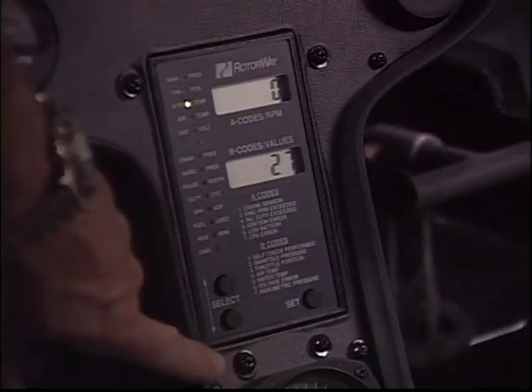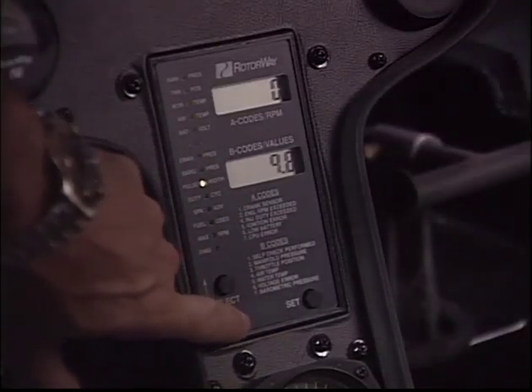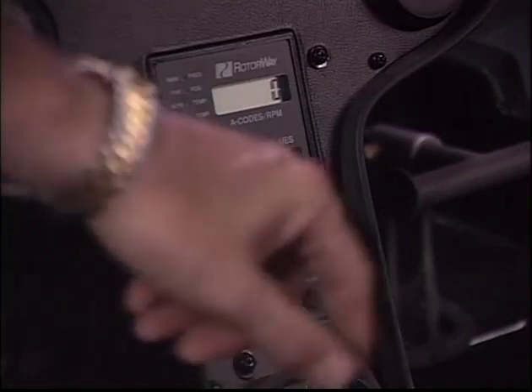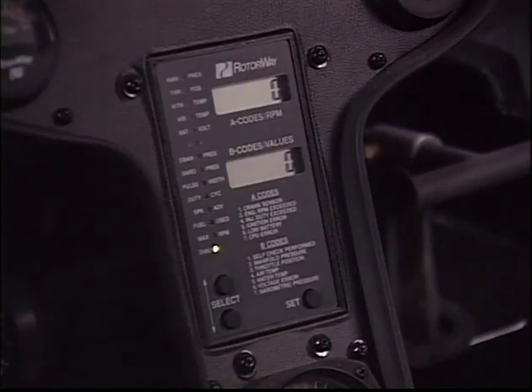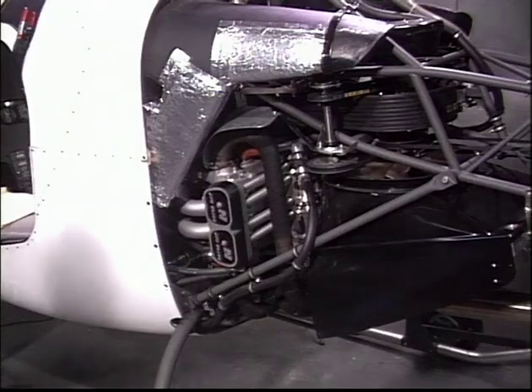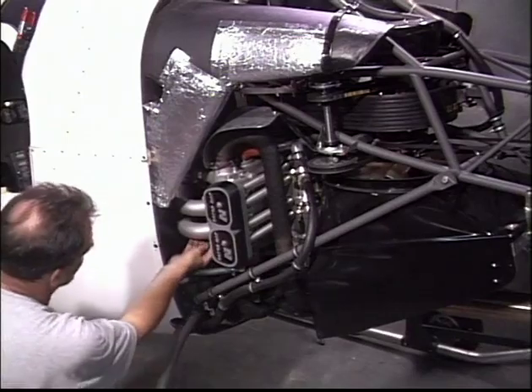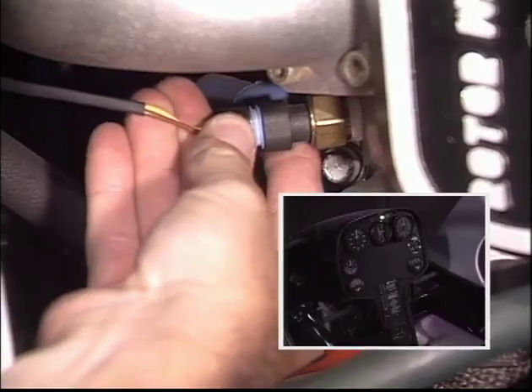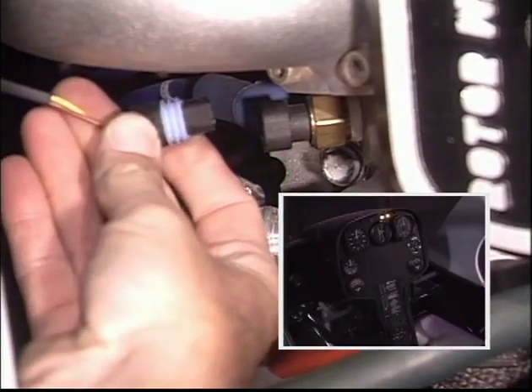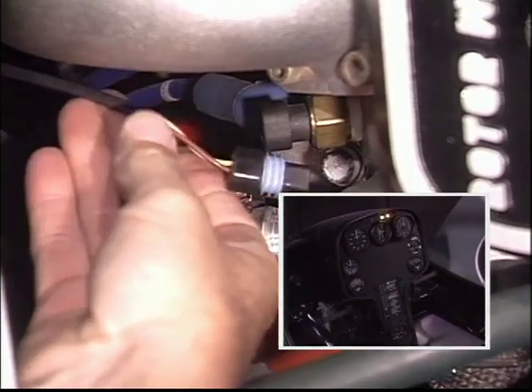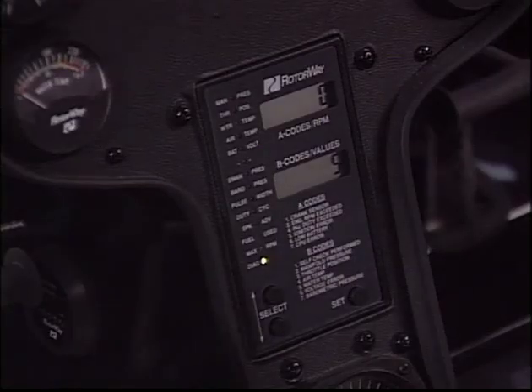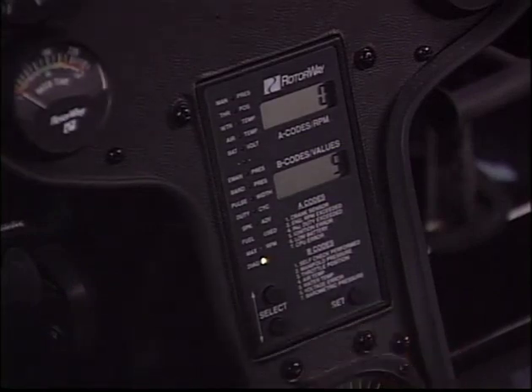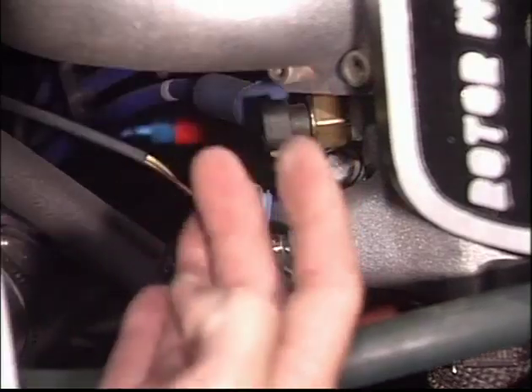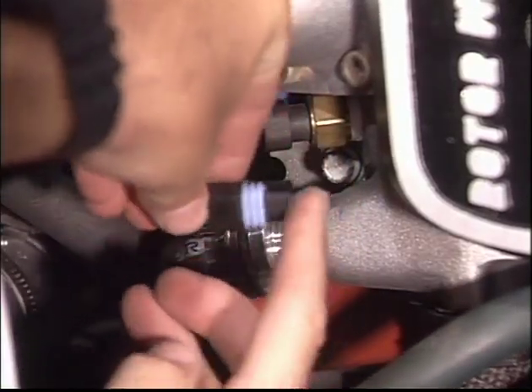Move the digital display to Diagnostics. The upper and lower readout should be 0. If an error code is displayed, refer to the Diagnostics section under Error Codes. Carefully disconnect the water temperature sensor plug. The yellow light on the instrument panel should activate. Number 5 should appear in the lower readout. Pressing the Set button should not clear the error. Carefully reconnect the plug.